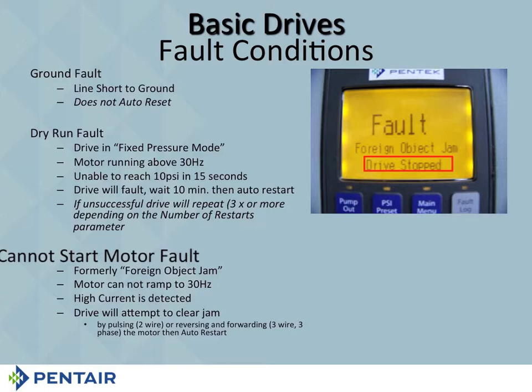If it can't, then it will fault and be drive stopped. If you see a cannot start motor fault, you need to pull the pump. You know that something is jamming up that motor and it can't start. If it is a ground fault, you must find the ground. Someplace between the pump and the motor, the pump and the drive, there is a ground, and it's picking up that ground. So you've got to fix that wire. You maybe nicked a wire putting it down, okay?